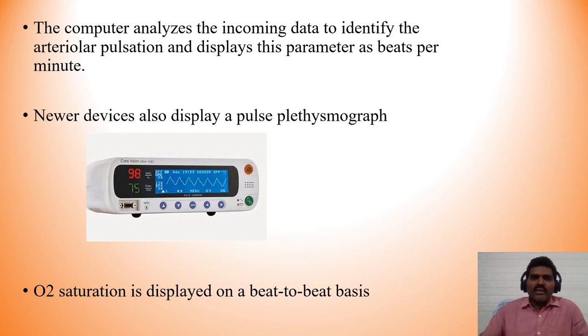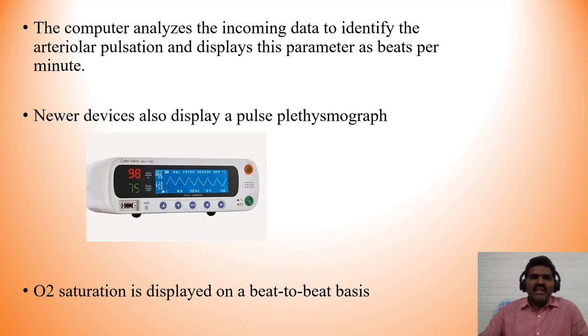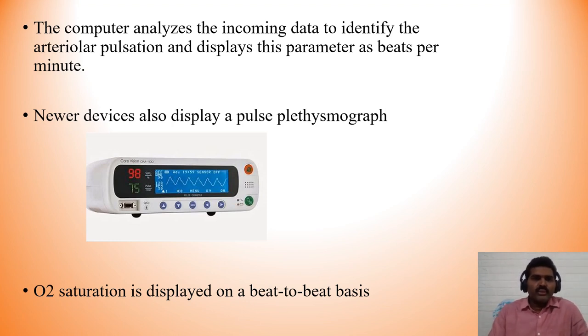Once the pulse oximeter is connected, the light is emitted, partially absorbed, and partially transmitted. The transmitted light is collected and the computer analyzes the incoming data to identify arterial pulsation, displaying heart rate in beats per minute. With each heartbeat, a wave is produced called the plethysmographic wave. Older pulse oximeters display only the numerical SpO2 value, whereas newer devices display the pulse plethysmograph waveform alongside the SpO2 percentage. Oxygen saturation is displayed on a beat-to-beat basis.